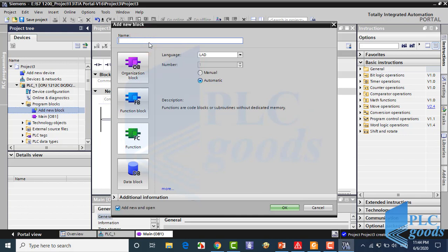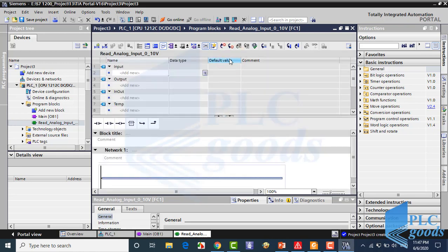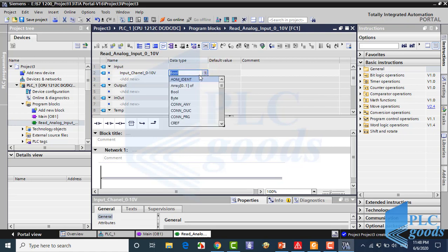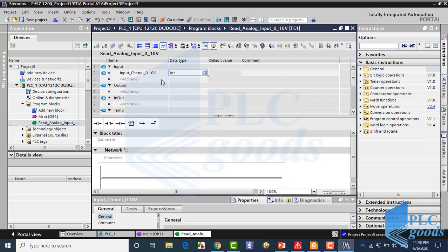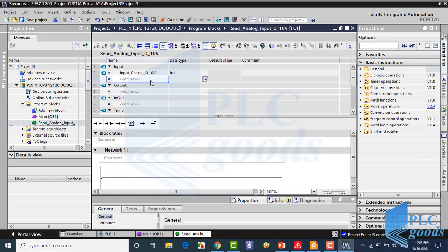Select 'Function' and write a suitable name. The first input of this function is from the analog channel. For 0 to 10 volt, this channel gives an integer number from 0 to 6C00 in hexadecimal format. The next inputs are the lower and upper values of the level sensor measurement, which will be 0 to 50 meters for this project.